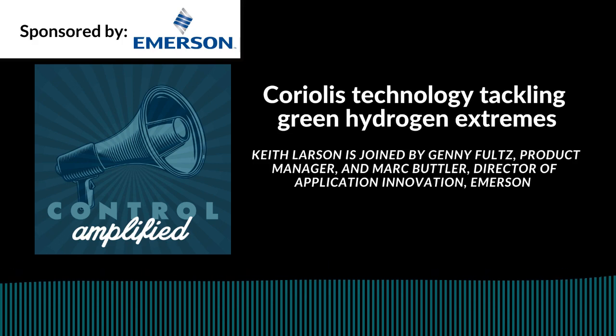So that's good. And one of the other things that we learned in the process of adapting our high-pressure gas meter lines to include the HPC015 and make it ready for hydrogen dispensing was how to use this new austenitic stainless steel alloy XM19, which gives us the strength but keeps flexibility in order to make the flow tubes that vibrate inside the Coriolis meter sensitive enough to be able to measure the hydrogen flowing through, and yet strong enough to contain the really high pressures involved.